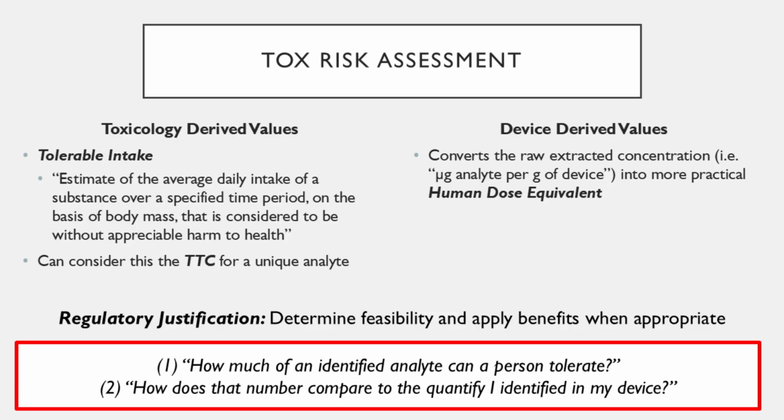That's where you can justify to a regulatory body, well, the benefits of my medical device are so beneficial that they outweigh any slight amount above this toxicological concern. The more life and death impact that your medical device might present, the more you can justify having exceeded some sort of tolerable intake. So that's what I mean by regulatory justification.